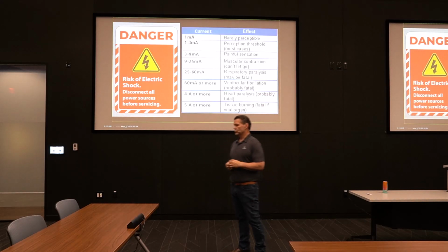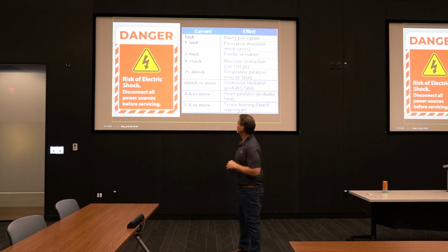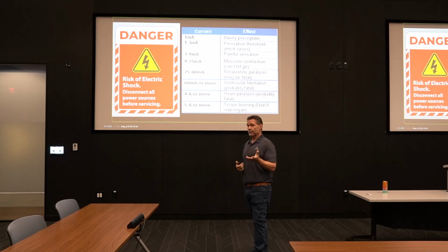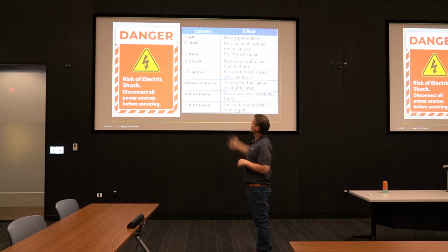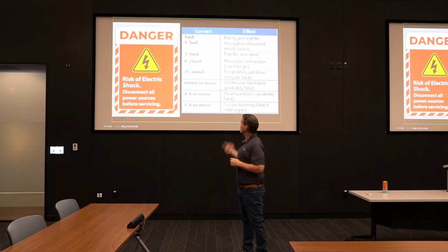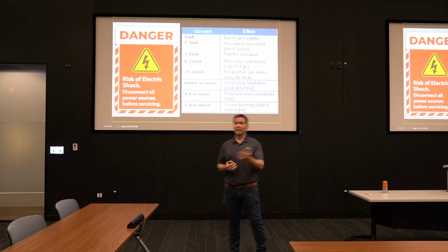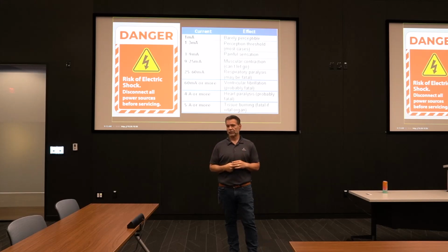So when it comes to shock, these are just some numbers for you here. mA is milliamp, which is 1/1000th of an amp. So at 1 to 3 milliamps, that's where most people start to feel it. 3 to 9, it becomes painful. At 4 milliamps, that's when a GFI will actually trip. GFIs are created to protect people. Breakers, you know, in a panel, a 20 amp breaker, it's made to protect equipment and wiring. It's not necessarily made to protect you, but a GFI is. GFIs are made to protect people. So that's why it has such a low threshold for tripping.